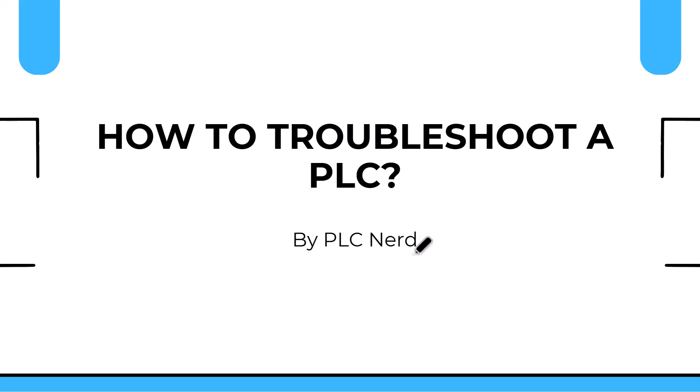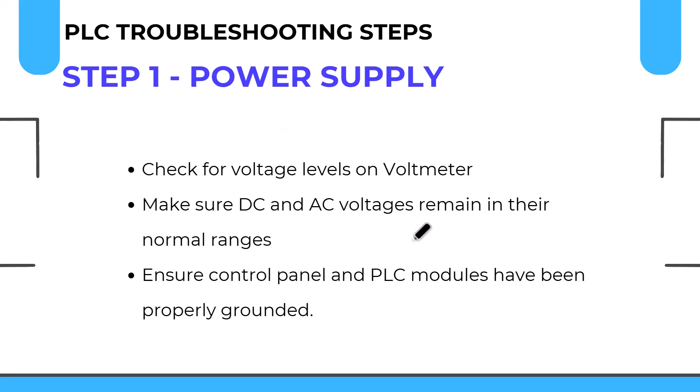Step one is to check the status of the power supply. Each PLC has a power supply module, whether integrated or separate. In our case it is the Siemens S7-300 power supply PS307. Make sure the input voltage is within the normal range, and the output voltage — in our case DC 24V — is correct. Ensure that each module of the PLC is receiving its proper power supply.